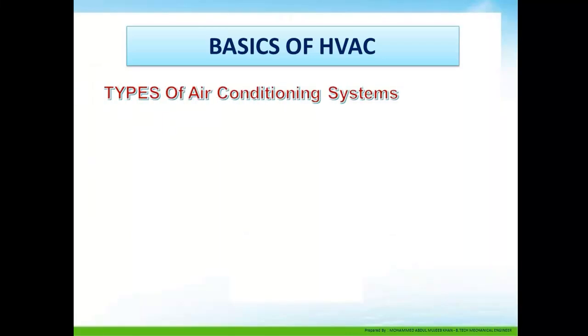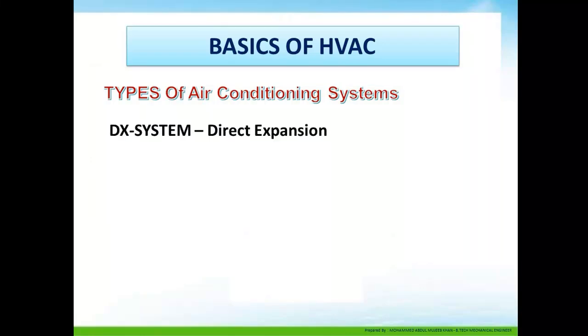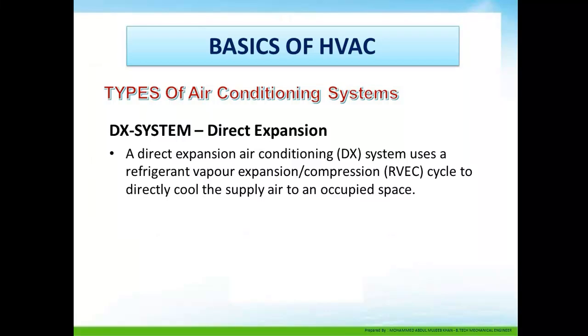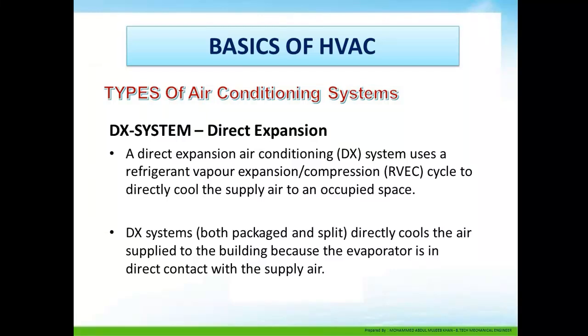Types of air conditioning systems. The basic type is DX — direct expansion. A direct expansion air conditioning system uses a refrigerant vapor compression cycle to directly cool the supply air to an occupied zone. DX systems — both package and split — directly cool the air supplied to the building because the evaporator is in direct contact with the supply air.